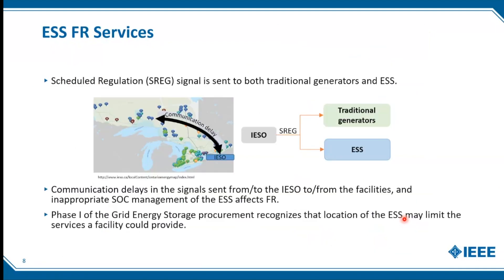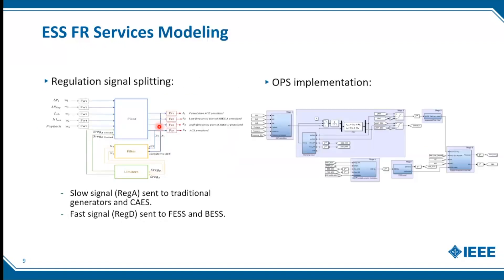Then we looked at applying energy storage systems — particularly flywheels and batteries — and what kind of impact they have on frequency control. This approach has been applied in the northeast of the US, where you divide the signal into two parts: a slow and a fast signal. One advantage is that you can use the fast response of energy storage for frequency regulation, leaving traditional generators for their role. The need for virtual inertia means you can use these fast energy services to regulate frequency.